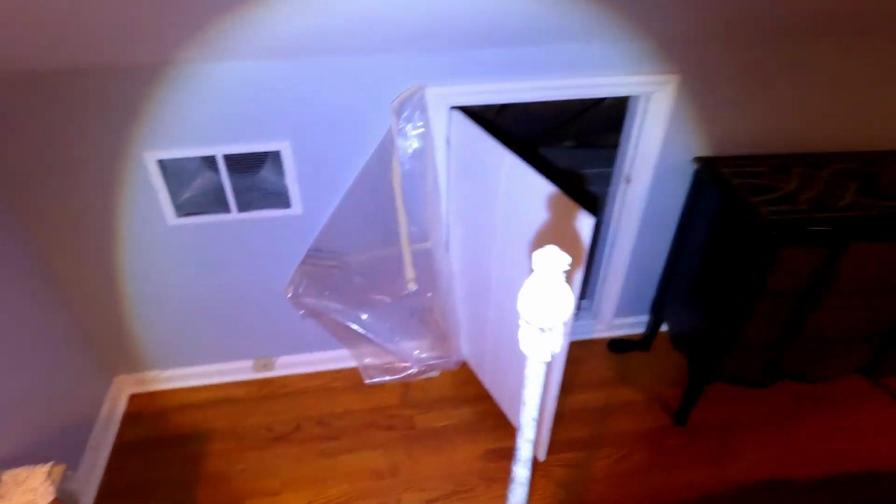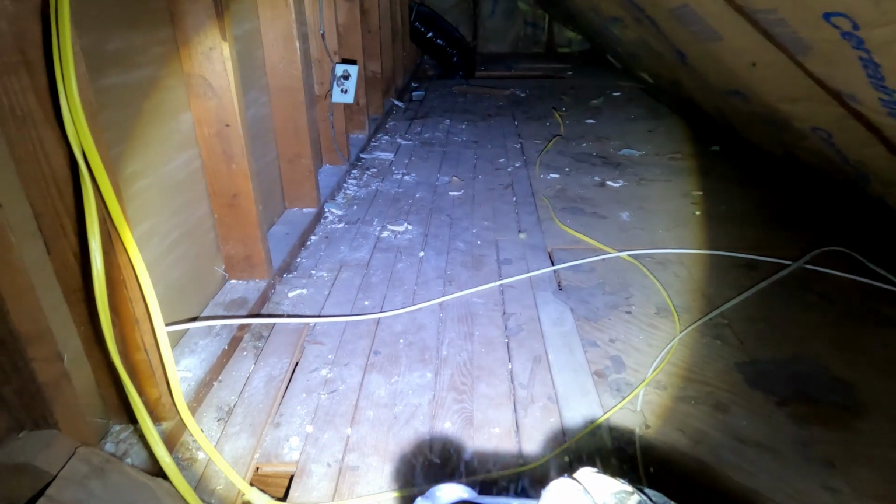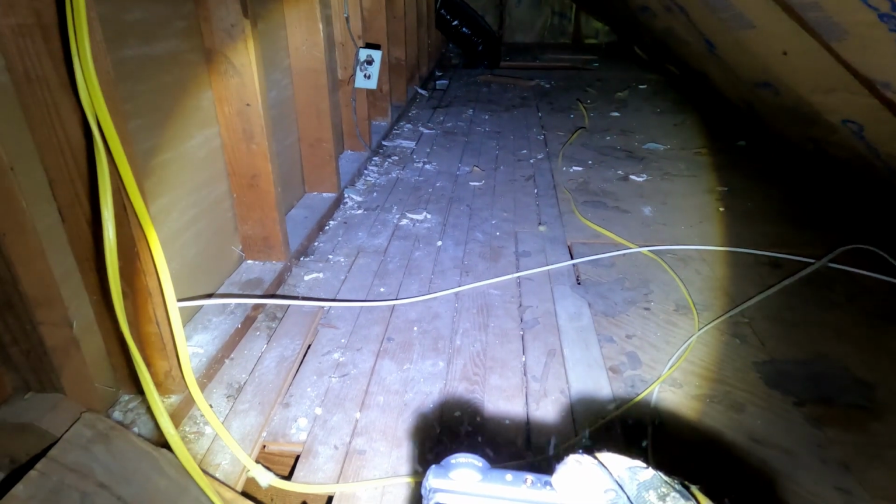For example, just one off the top of my head, yesterday it was a knee wall on a Cape Cod. At first sight, when I put my head into the knee wall attic, I saw a bunch of insulation falling down, and I could feel, even in myself, that I didn't really feel like going further. But with just a little extra effort, I was able to push some things to the side, and I had to get under the duct, which was a little tight for me. I'm going on 50 years old now. But once I got around, I was able to see everything, and that gave me confidence to speak to the customer. I wasn't guessing about what was behind it.